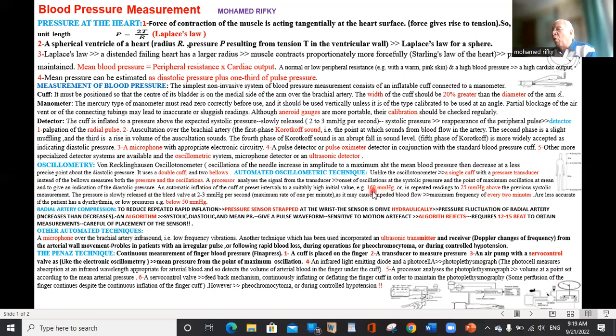The system begins first of all by increasing the pressure to 160 millimeter mercury, and then after that it increases the pressure by 5 millimeter above the recorded previous measure. Of course, the rate, as we said before, is 2 to 3 millimeter mercury per second. Of course, the problem is that the continuous measurement impedes the blood flow. So the maximum is every 2 minutes whenever we have a problem that we are in need of continuous measure of blood pressure. Of course, it is less accurate in the presence of arrhythmia and pressure below 50 millimeter mercury.